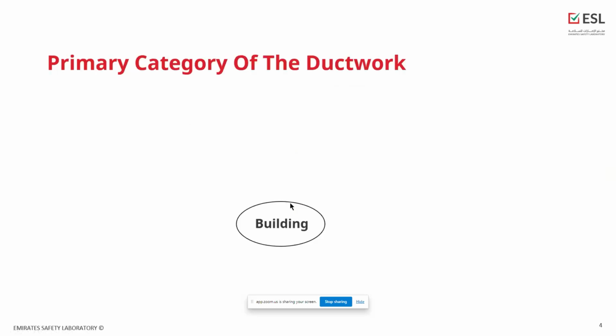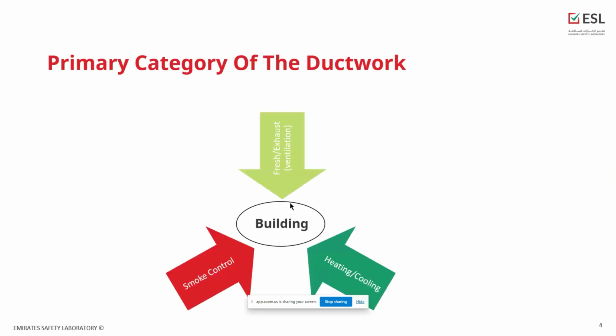So the primary category of the ductwork: normally we can find in most buildings fresh and exhaust ductwork, which we call ventilation. And specifically for this point I just want to highlight there is a connection between ventilation as fire rated ducts, and also ventilation as air distribution, normal air distribution in the building, for heating and cooling, as well as smoke control. We'll be going through the definition of all these three categories of ductwork.